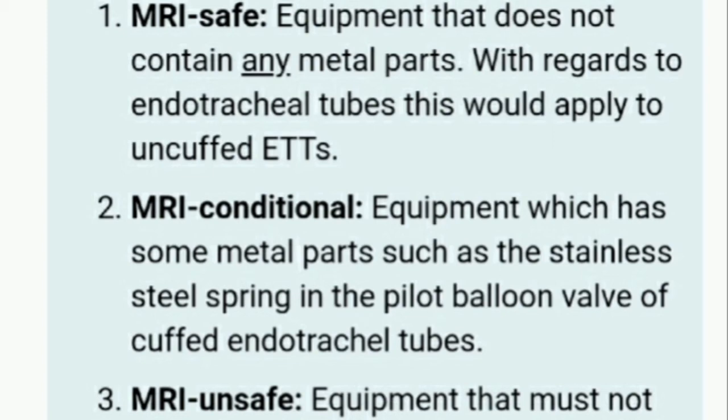The second is MRI conditional. Equipment which has some metal parts such as the stainless steel spring in the pilot balloon valve. And then the third is MRI unsafe, equipment that must not be used in an MRI environment.